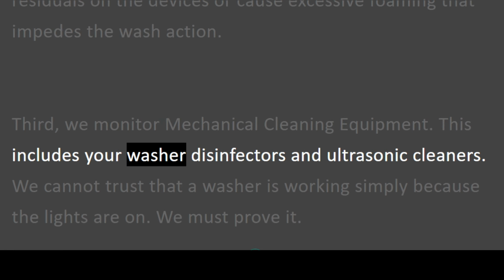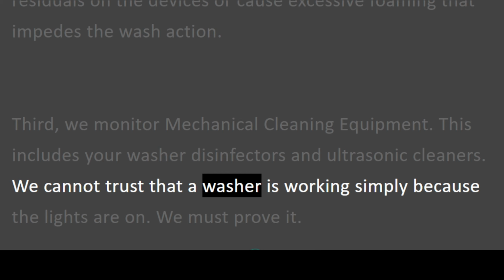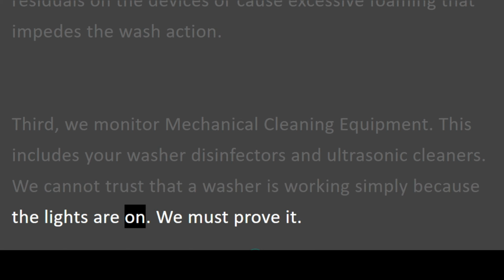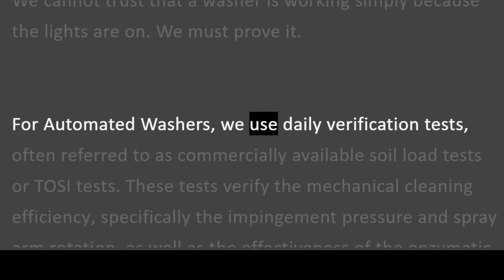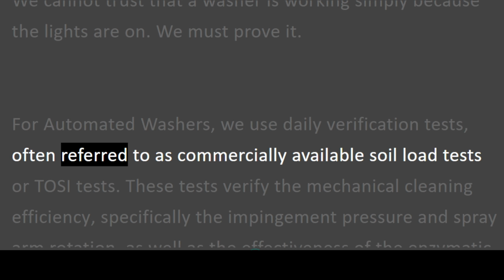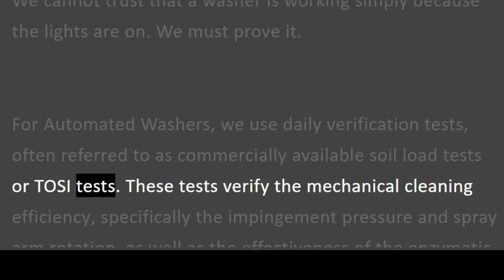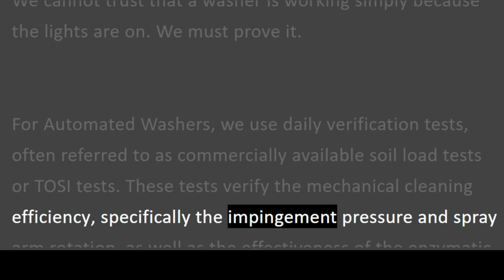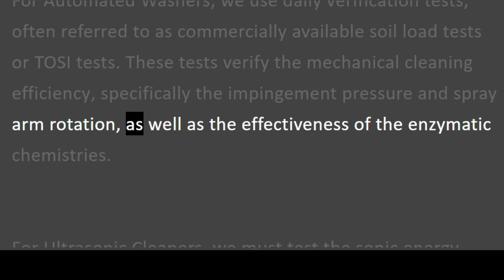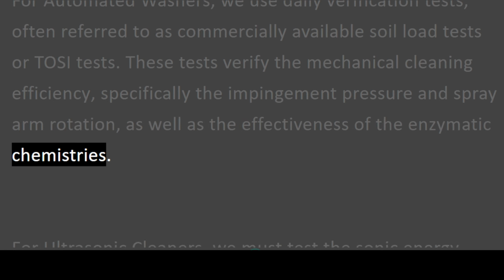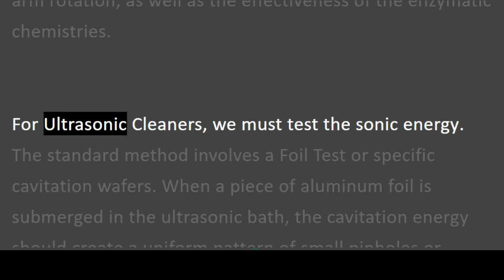This includes your washer disinfectors and ultrasonic cleaners. We cannot trust that a washer is working simply because the lights are on. We must prove it. For automated washers, we use daily verification tests, often referred to as commercially available soil load tests or TOSI tests. These tests verify the mechanical cleaning efficiency, specifically the impingement pressure and spray arm rotation, as well as the effectiveness of the enzymatic chemistries. For ultrasonic cleaners, we must test the sonic energy.